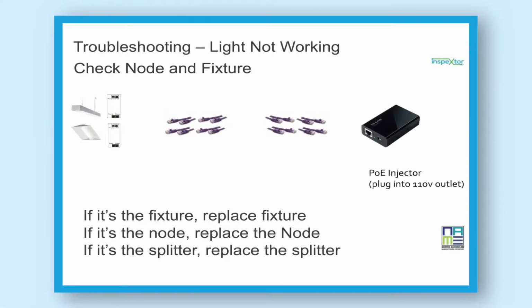It's easy to just take it off and test that on the fly. But the idea is I would test from one side, where the yellow cable is, all the way to the fixture. So if I know that's good, I'm not testing anything in between. There's no point. I don't have to divide the problem, because it's either on the fixture side or on the switch side. It can't be anywhere in between.